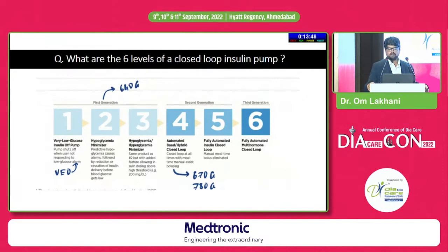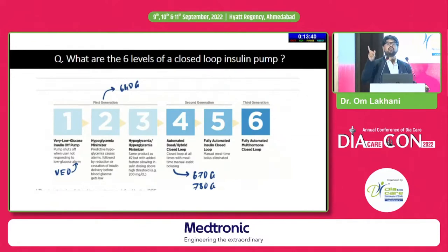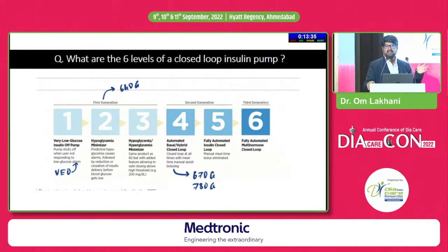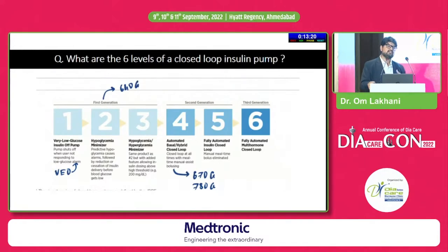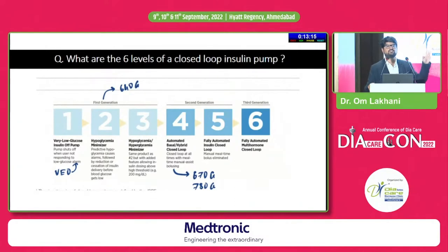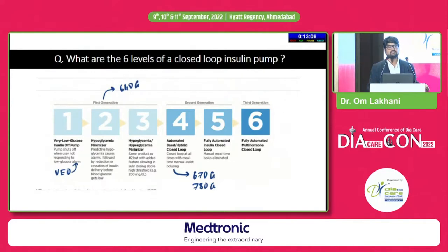Finally, we have the fully automated multi-hormone closed-loop device — generation 6. Clinical trials have already been published for such pumps. One is known as ILET. It's not yet available in India, but it has multiple hormones just like the human pancreas — insulin, glucagon, and other hormones can be incorporated. If glucose goes low, it shuts off insulin and also releases glucagon, and vice versa. It can do multiple things simultaneously — that's the generation 6, multi-hormone closed-loop device.